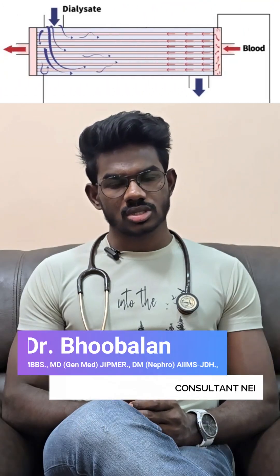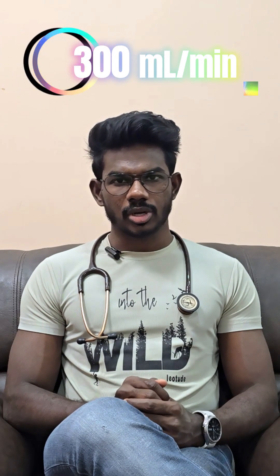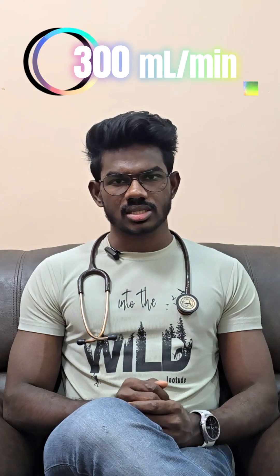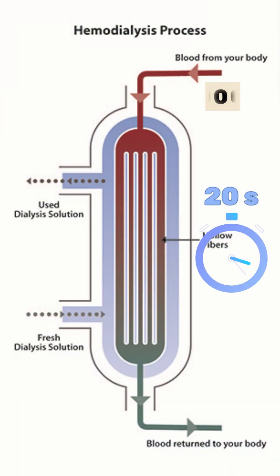A dialyser holds roughly 100 ml of blood at any given time. Imagine blood entering the dialyser with a urea level of 100 units. If you run the blood at 300 ml per minute, that 100 ml stays inside the dialyser for only about 20 seconds. With that short contact time, urea may drop from 100 to 40 units in a single pass. This 60% reduction between the inlet and the outlet blood urea level is what we call the extraction ratio.